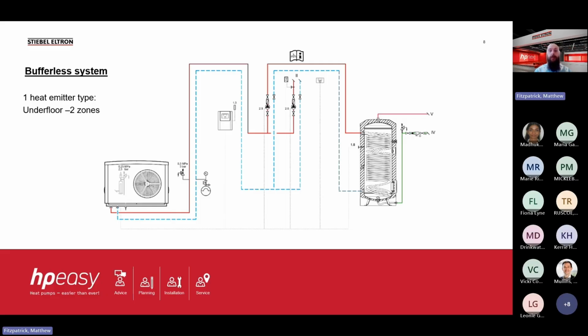In most cases, we use a 2-pump system, a loading pump for the heating system and a loading pump for domestic hot water, to allow us to have PWM controls on both. If you were to use a diverter valve, then you may fall foul because you may set the flow rate for your heating, but then the flow rate that you've set on a singular pump isn't sufficient for your domestic hot water. However, because we're targeting higher temperatures in the hot water cylinder, we need to ensure that delta T is the best we can possibly get it. Otherwise, we have a backlog of energy, of heat, that cannot reach the cylinder and transfer into the domestic hot water, and will return back to the heat pump, which means short run cycles and potentially faults on the controller and the heat pump.